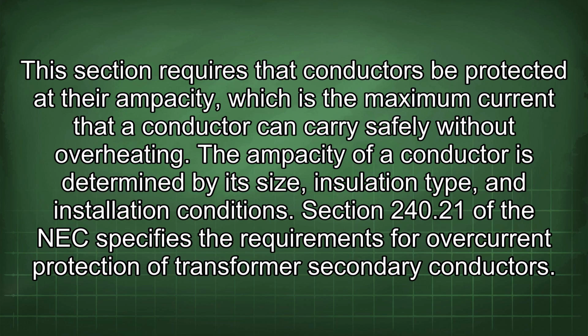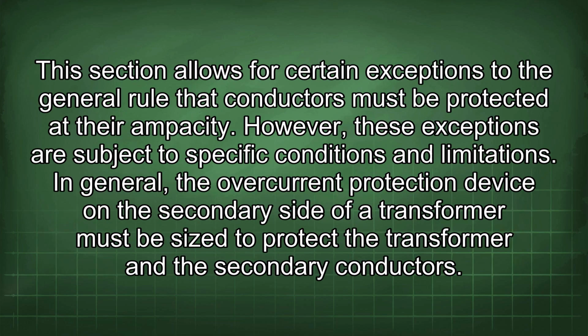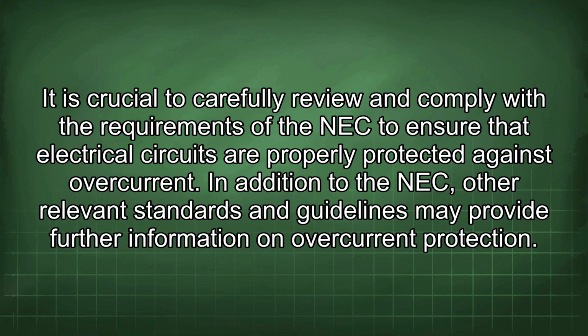Section 240.21 of the NEC specifies the requirements for overcurrent protection of transformer secondary conductors. This section allows for certain exceptions to the general rule that conductors must be protected at their ampacity. However, these exceptions are subject to specific conditions and limitations. In general, the overcurrent protection device on the secondary side of a transformer must be sized to protect the transformer and the secondary conductors. It is crucial to carefully review and comply with the requirements of the NEC to ensure that electrical circuits are properly protected against overcurrent.